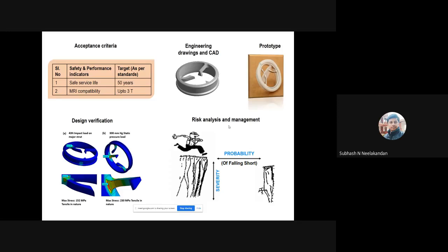And post 2015, we are following the set of standards insisted on by the medical device regulation. I will come to the details later. As a part of that, whichever device we are developing, there should be an associated risk analysis and management, first of all in the design stage. All the design verification activities should be undertaken based on the risk analysis and management.